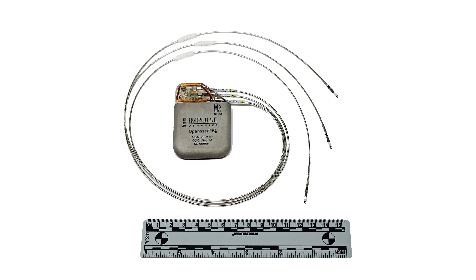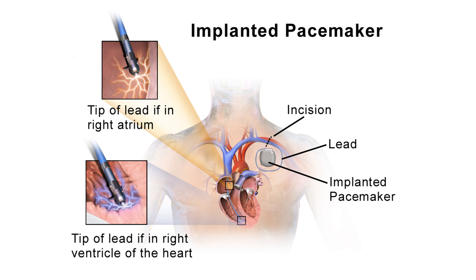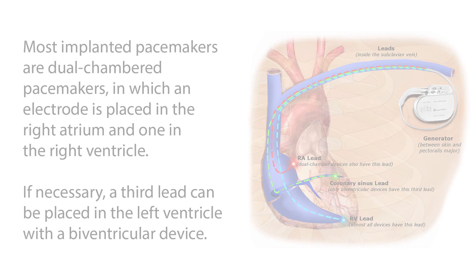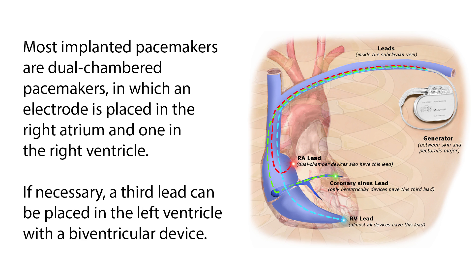Permanent pacemakers are used to treat various bradycardiac arrhythmias and are implanted during a brief surgical procedure, usually under local anesthesia. The electronic control center, called the pulse generator, is encased in titanium with a lithium iodide battery inside that lasts 5–12 years. The pulse generator is attached to one or more lead wires threaded through large blood vessels in the upper chest into the heart. Small electrodes at the ends of the leads attach to the inner surface of the heart, pick up the heart's natural electrical signals, and deliver the pacing pulse from the generator. The pulse generator is usually placed under the skin below the collar bone. Most implanted pacemakers are dual-chambered, with an electrode in the right atrium and one in the right ventricle. If necessary, a third lead can be placed in the left ventricle with a biventricular device.